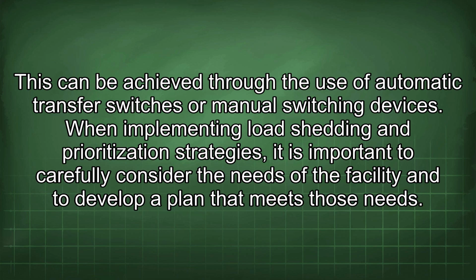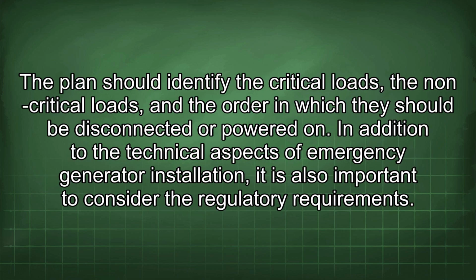When implementing load shedding and prioritization strategies, it is important to carefully consider the needs of the facility and to develop a plan that meets those needs. The plan should identify the critical loads, the non-critical loads, and the order in which they should be disconnected or powered on.